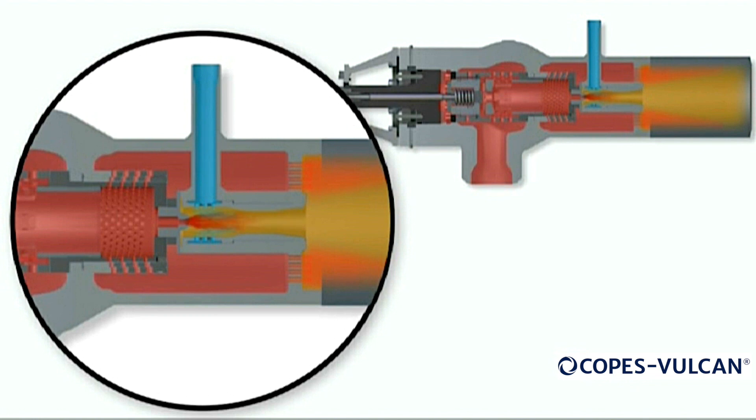Water dropout can be very damaging as cold water will track along the bottom of the inside wall of the downstream pipe, while uncooled superheated steam travels along the top and sides.